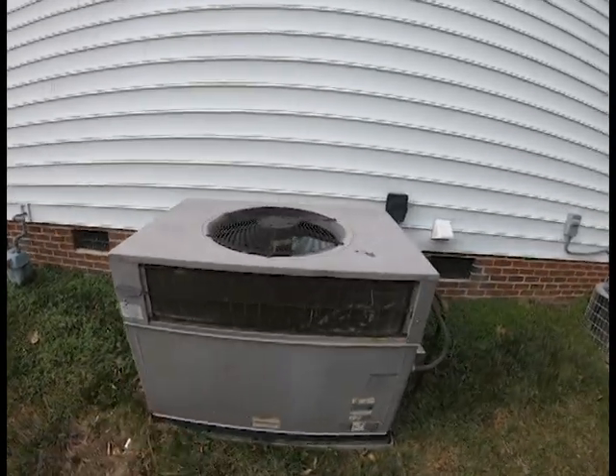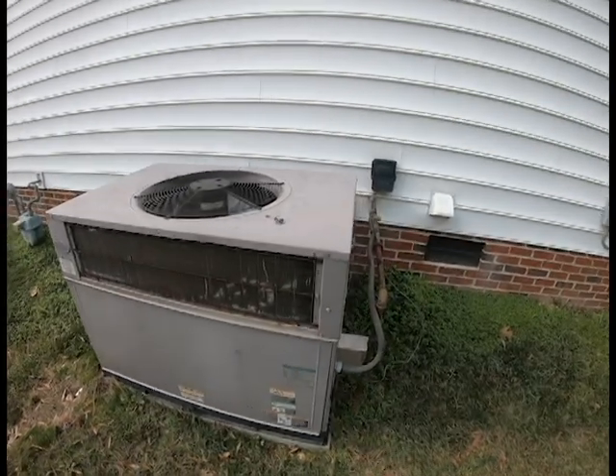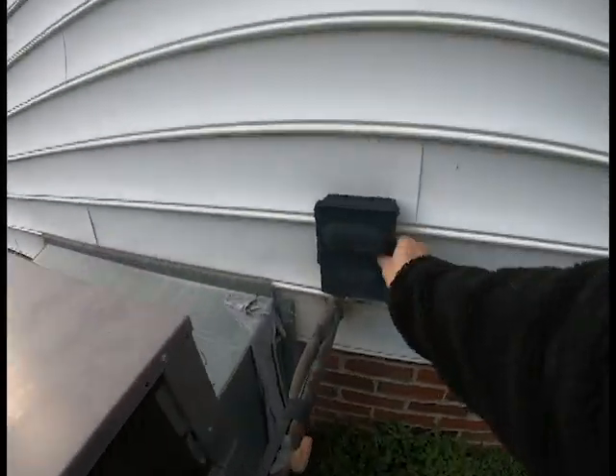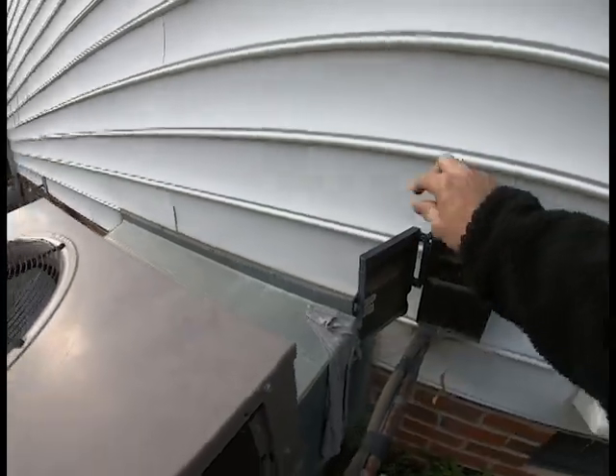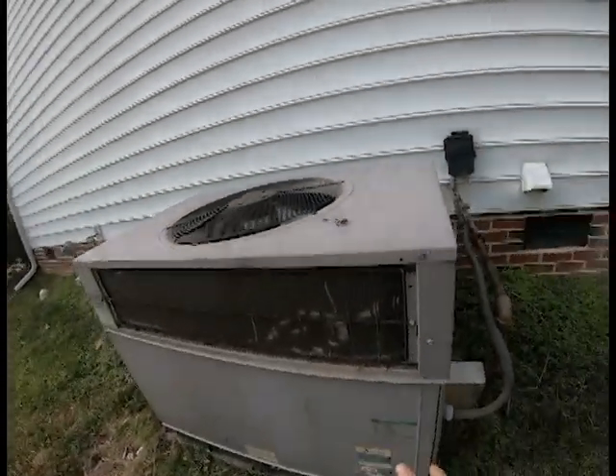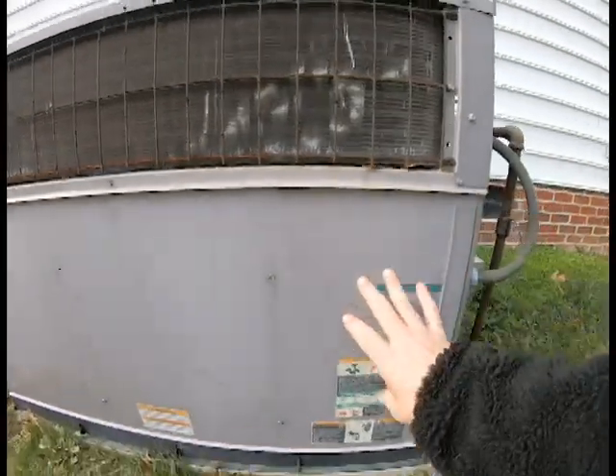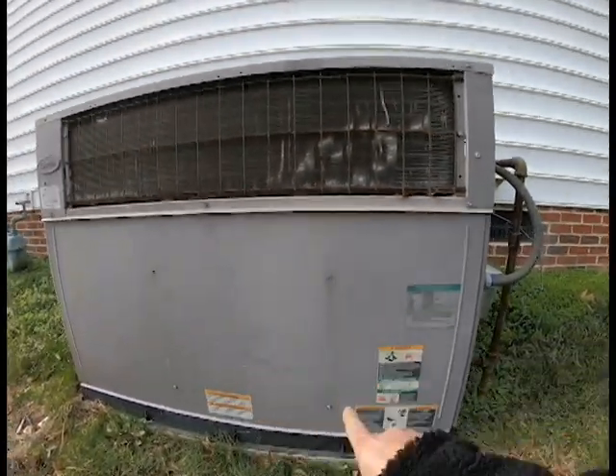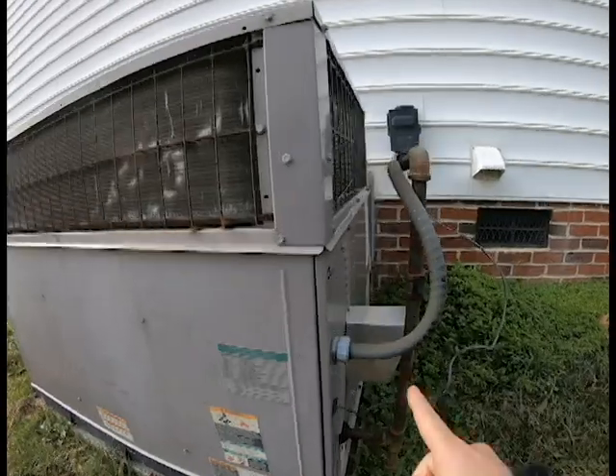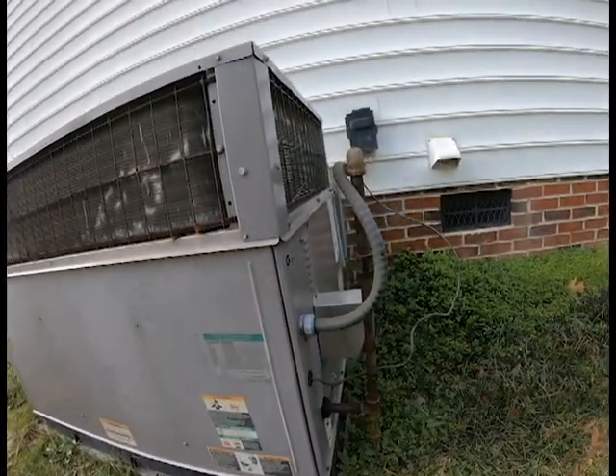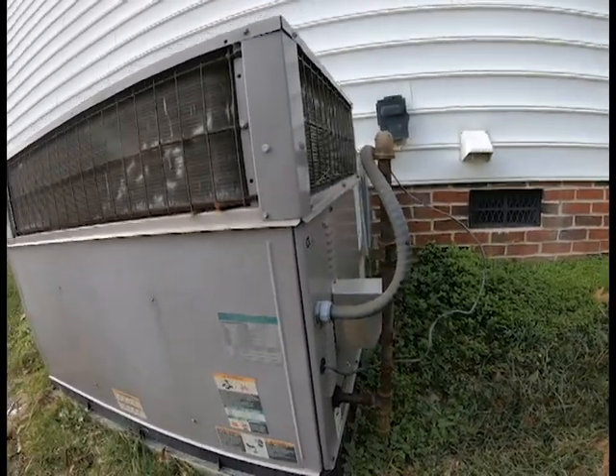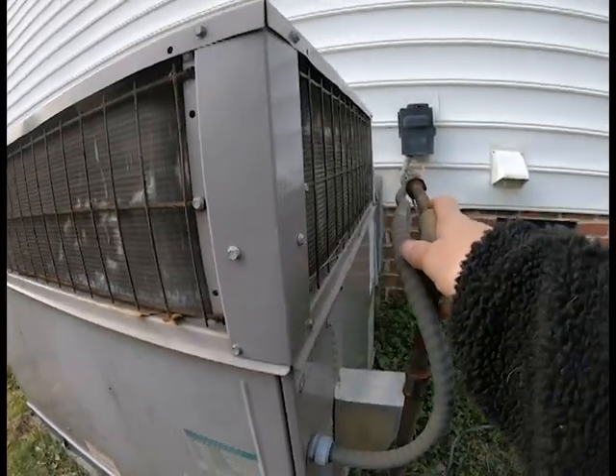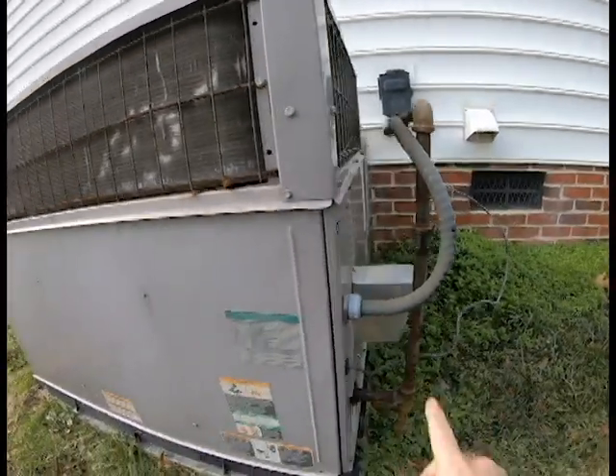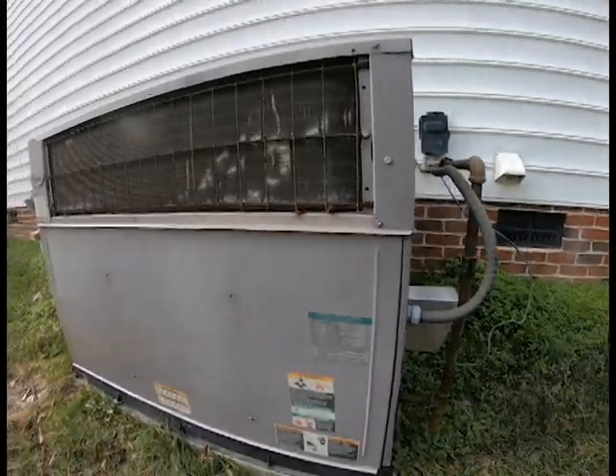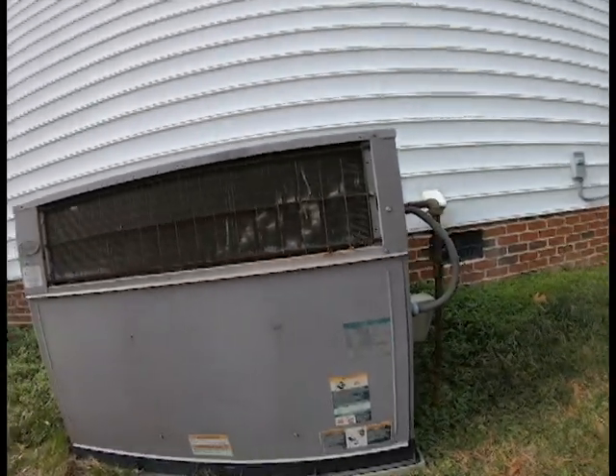Okay, here's the gas pack we're changing the heat exchanger on. The first thing we're going to do is remove power to our unit and let everything get turned off. The heat exchanger sits behind this cabinet here, so first we need to remove our covers. This side panel is probably going to come off since a lot of times it comes out the side. We're going to need to undo our gas line and take our electrical out. So let's go ahead and start taking off our cover plates.